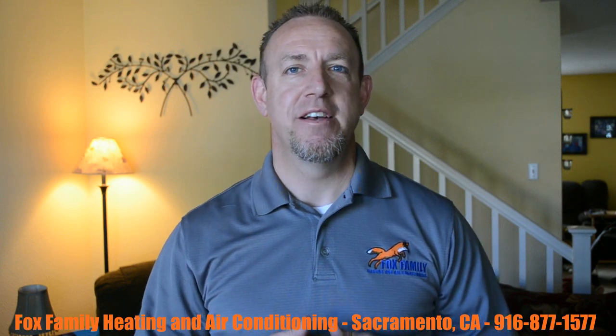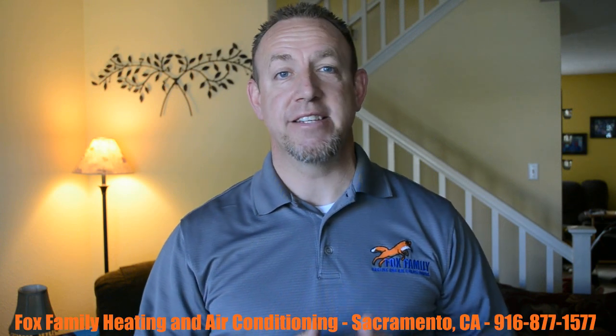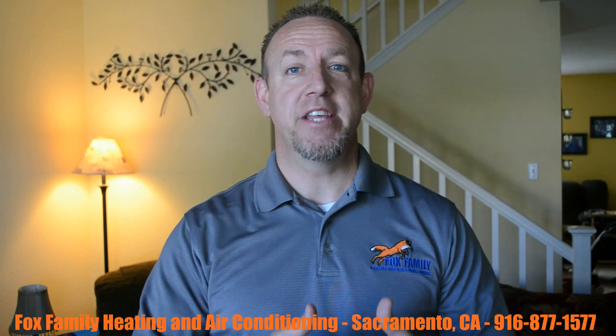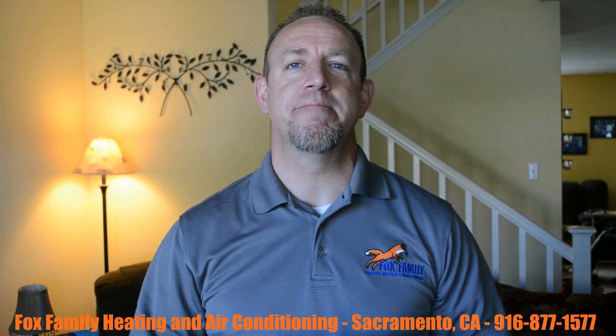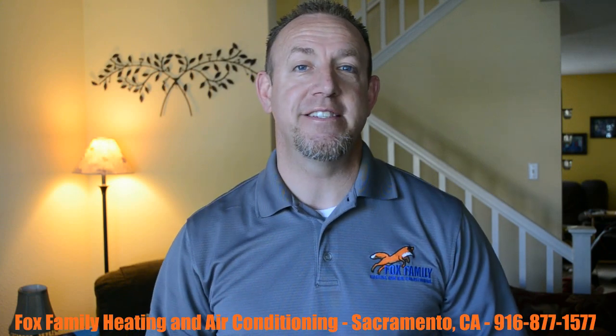Fox Family Heating and Air Conditioning has a thorough process to evaluate your AC repair needs. We start at the most likely source of the problem, in this case, the outdoor unit, and start by visually checking for anything that looks abnormal. We're looking for burning or black marks inside the control panel, burnt or charred wiring, loose wires, maybe a capacitor that's obviously blown. If we see everything inside the control panel looks fine, then we listen for any noises or humming that might be coming from the system. If the system still isn't running, we'll use our meters and gauges to determine any more technical issues that might be going on with your AC. This brings us to check the voltage readings at the contactor, capacitors, condenser fan motor, and the compressor, which is the heart of your AC system.